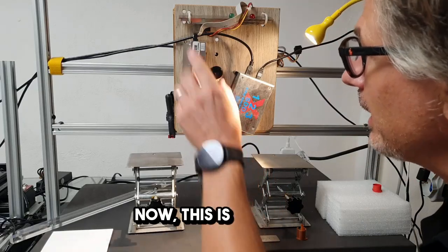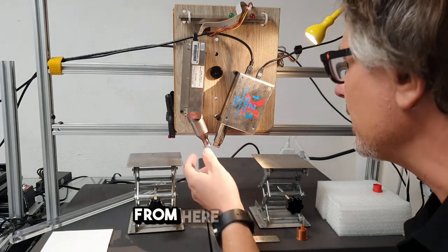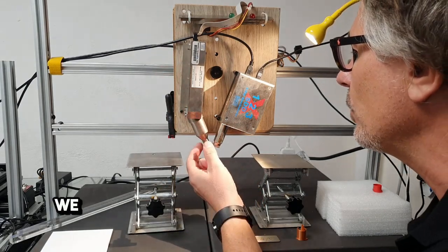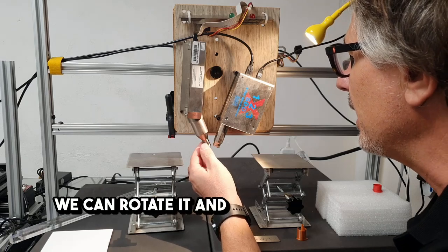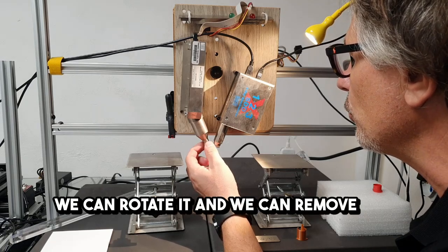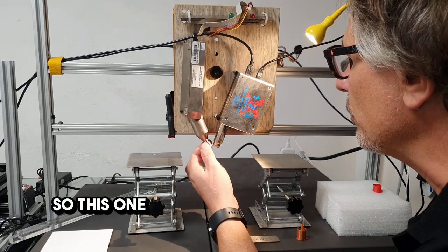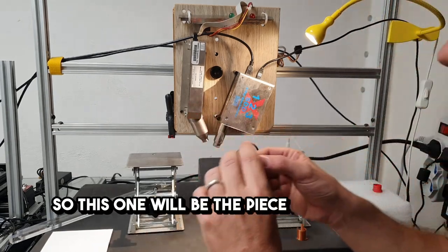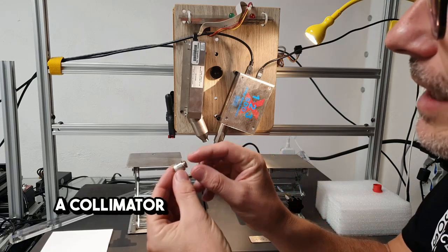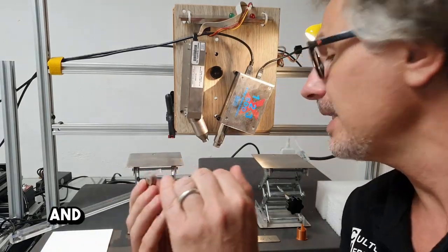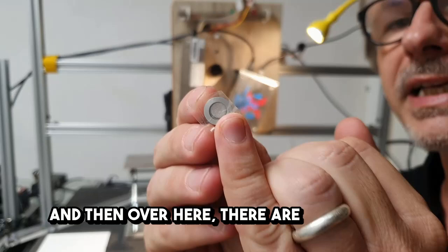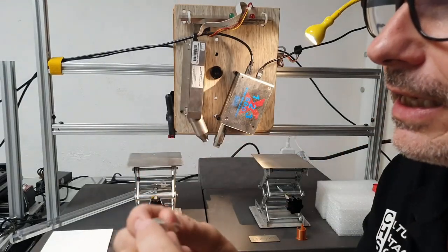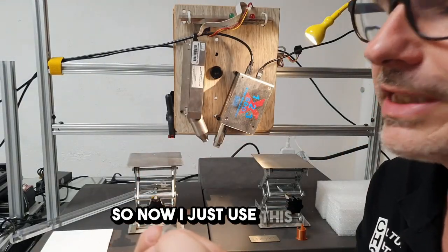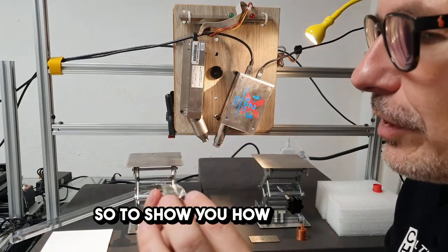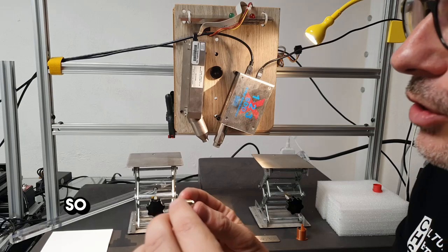So now this is our tube. From here, we can rotate it and we can remove this part. So this one will be the piece where there is a collimator inside, so to have a precise spot, and then over here there are the filters. So now I just use this tape so to show you how it is done.